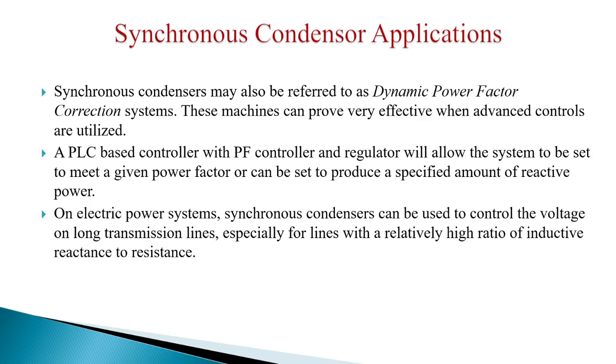Synchronous condensers may also be referred to as dynamic power factor correction systems. These machines can prove very effective when advanced controls are used. So a PLC based controller with power factor controller and regulator will allow the system to be set to meet a given power factor or can be set to produce a specified amount of reactive power. What is PLC here? Programmable logic controller.